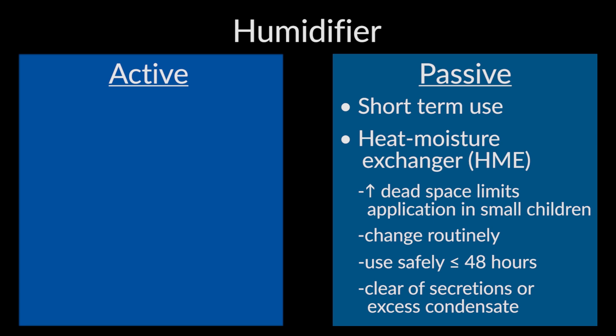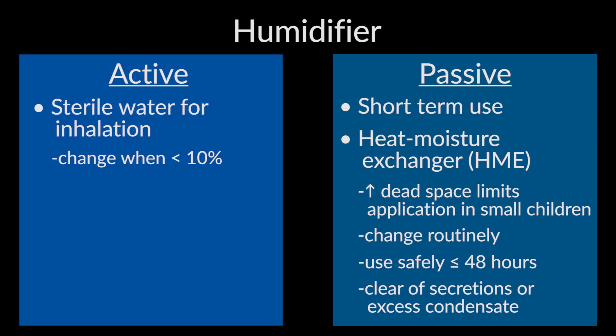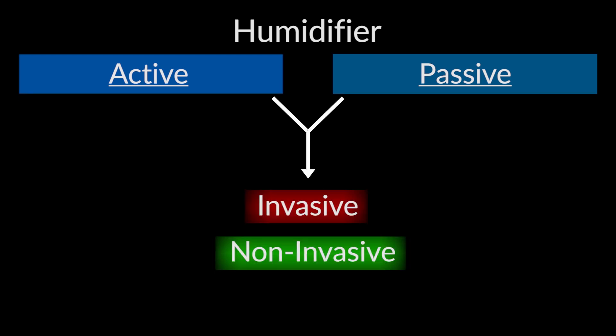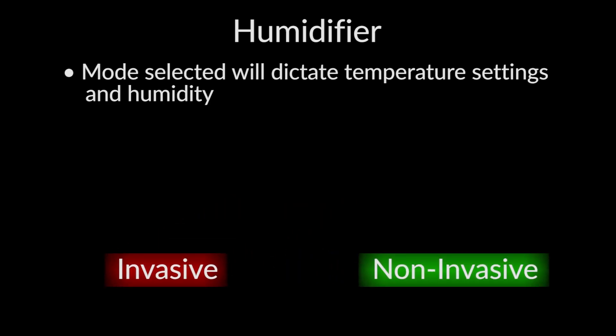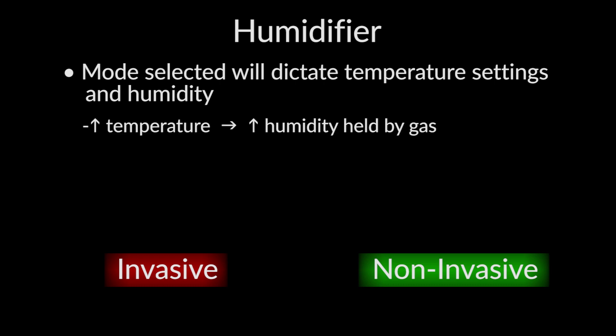The majority of mechanical ventilation will require active humidification. We need to assess that there is sufficient sterile water for inhalation, and I recommend that it is changed with 10% or less remaining to avoid running a circuit dry. We also need to ensure that our humidifier is set to the appropriate mode for the patient application. Most humidifiers and mechanical ventilators can accommodate both invasive and non-invasive ventilation. The choice will dictate our available temperature settings and the amount of humidity held by the gas. Remember, the warmer the temperature, the greater the amount of humidity carried by the gas.